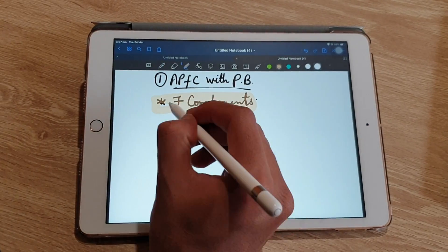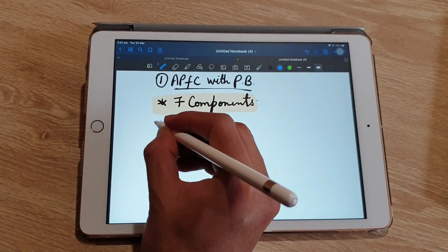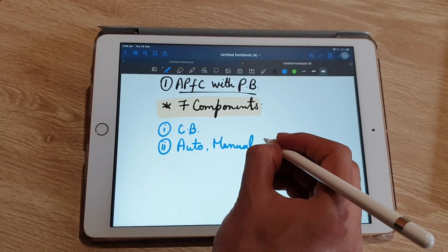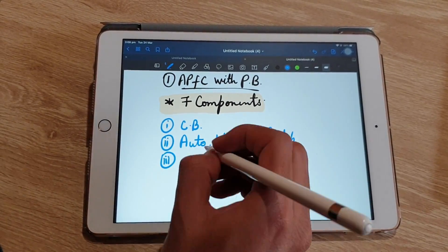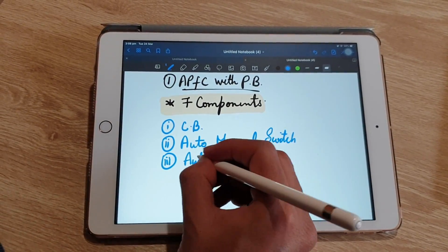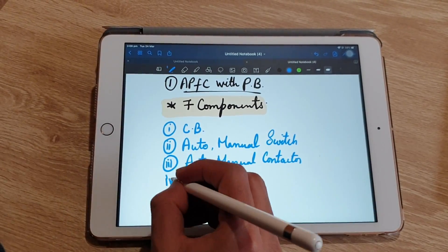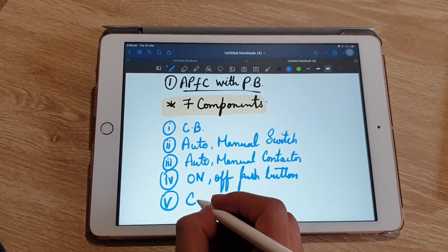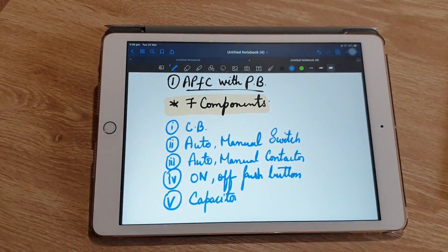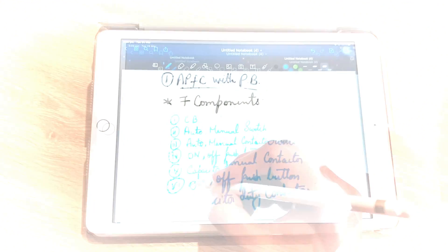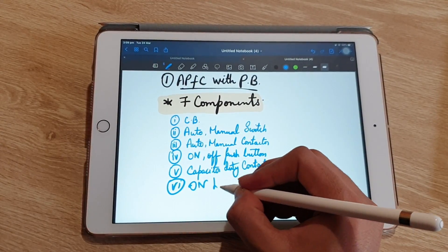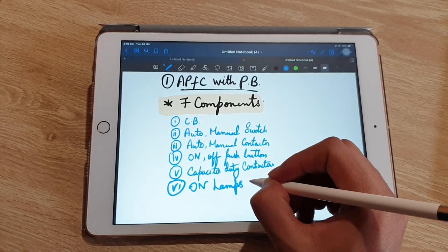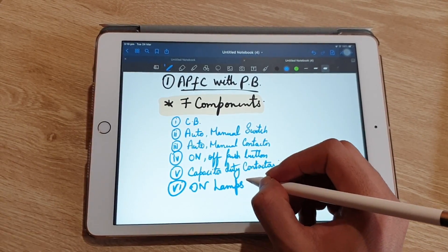An APFC panel with push button has seven main components: first is a circuit breaker, second is an auto-manual switch for switching between auto and manual mode, third is auto-manual contactors, fourth is on-off push buttons, fifth is capacitor duty contactors which we call CDCs, sixth is an on indicator, and the last one is busbars and wires for wiring of this panel.